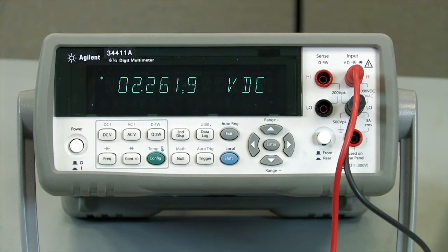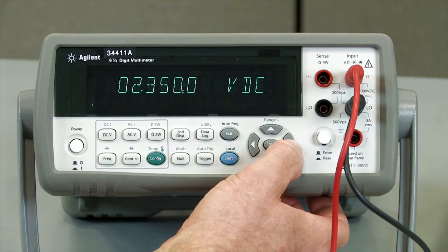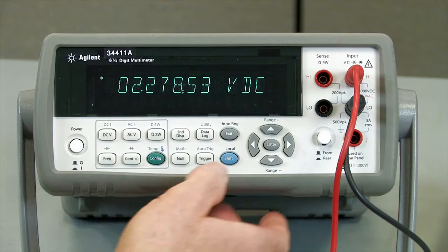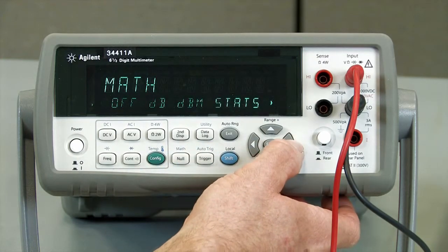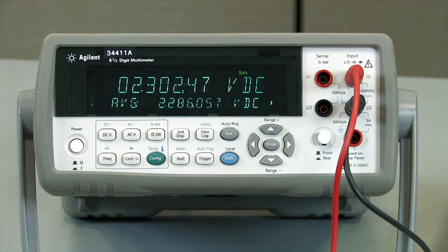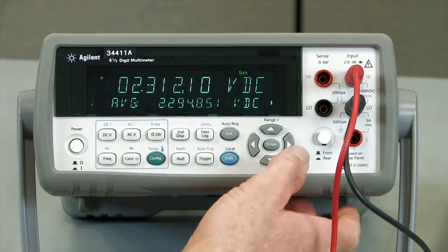So the default setting is one power line cycle. I'm going to go ahead and move up to 10 power line cycles. So we slowed the reading rate down. Again, I'm going to turn math on. But you can see it's much more stable integrating over time.